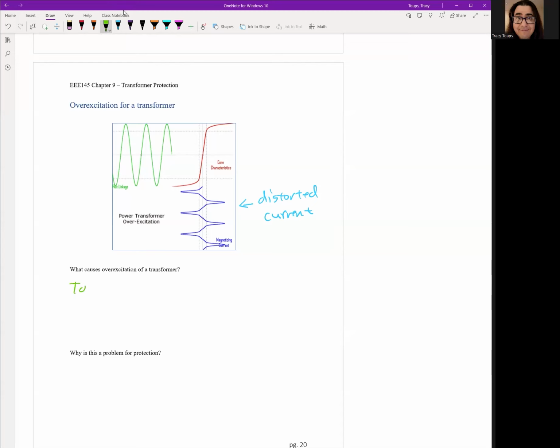So again, too much voltage. And somebody will ask, what's too much voltage? It's more than the transformer is rated for. If my transformer is rated for 115 kV and I use it for a 138 kV system, you might be running into overexcitation. If I use it for a 230 kV system, I'm way higher than what the transformer is rated for. For sure, I'm going to run into some overexcitation problems. Most likely, you're going to damage the transformer.